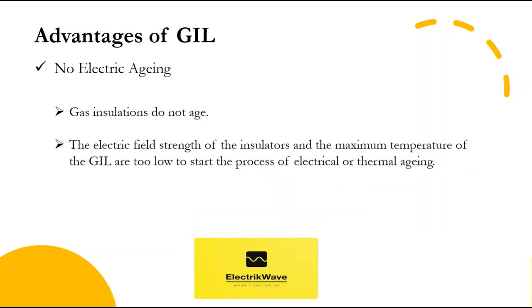GIL has no electric aging. Gas insulations do not age — the best example is an overhead line with ambient air as insulating gas. The electric field strength of the insulators and the maximum temperature of the GIL are too low to start the process of electrical or thermal aging. This has been proven using long-term measurements in independent laboratories and by extensive experience with the equipment in the network. The first GIL installations have been in operation since 1974, with results reported by CIGRE.